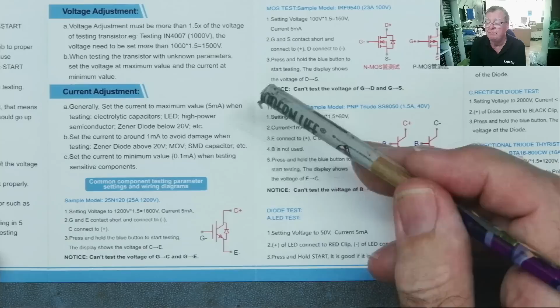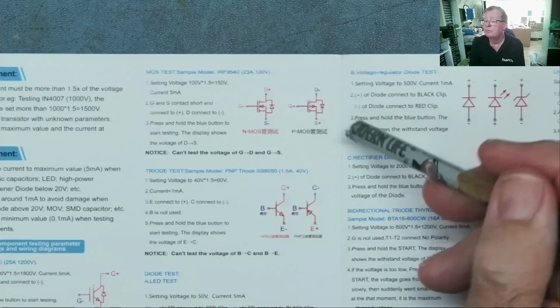So here's some examples. We have an IGBT here: set voltage at 1200 times 1.5, about 1800, and 5 milliamps. It's saying short the gate to the emitter so the gate will not float. Press and hold the blue button to start testing, and it will give you the breakdown voltage across collector to emitter.